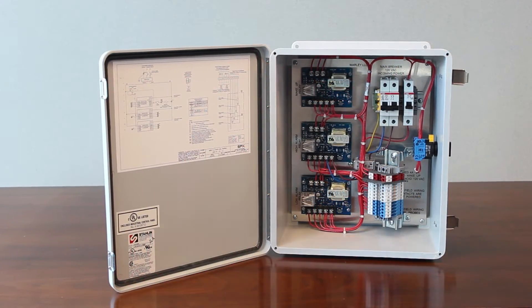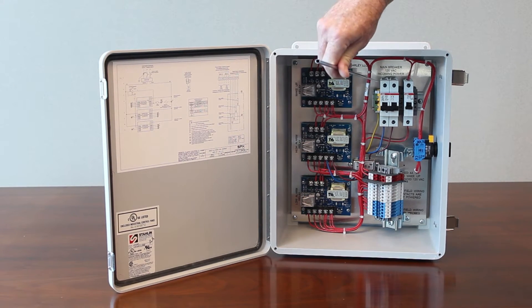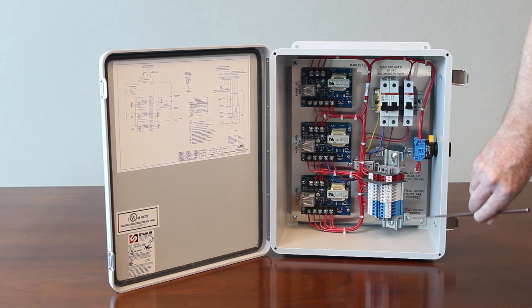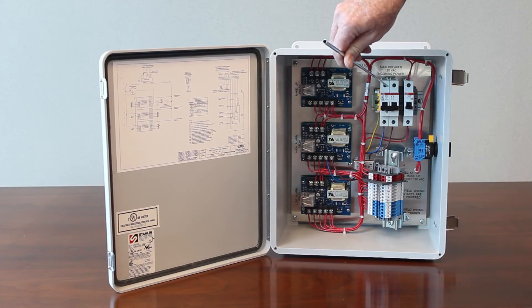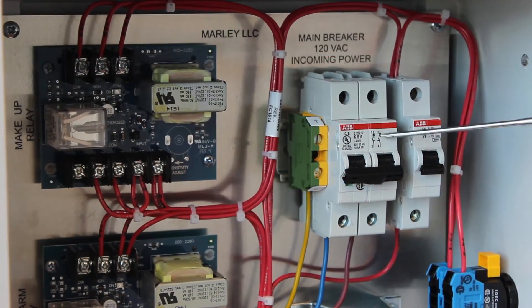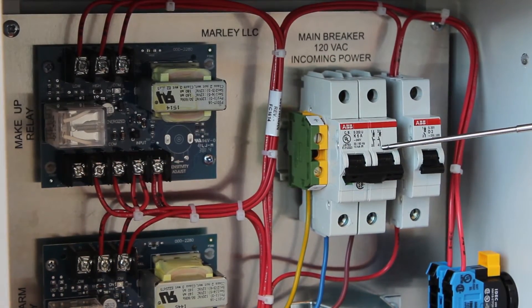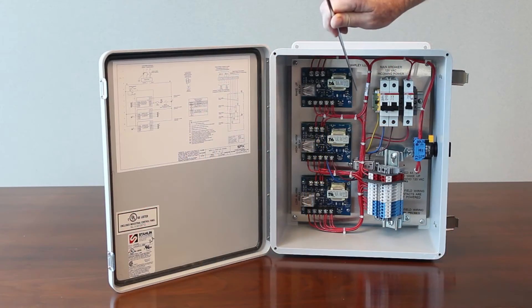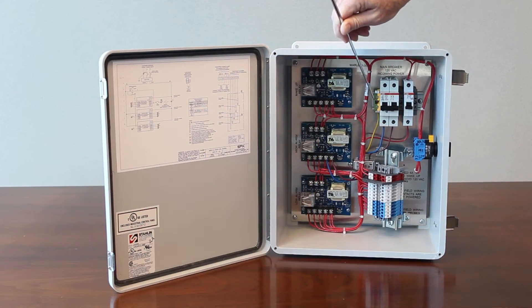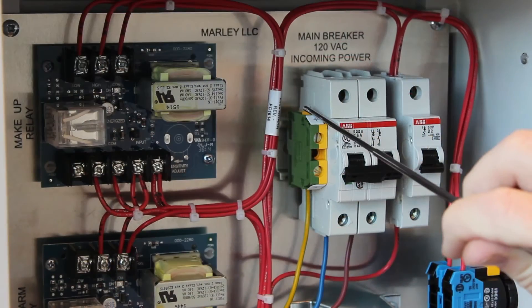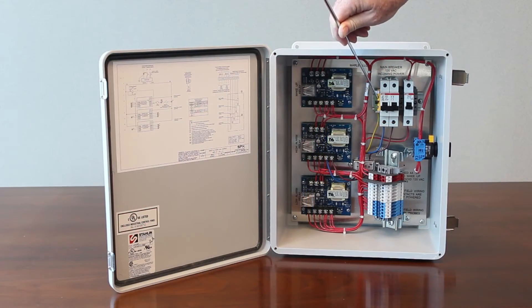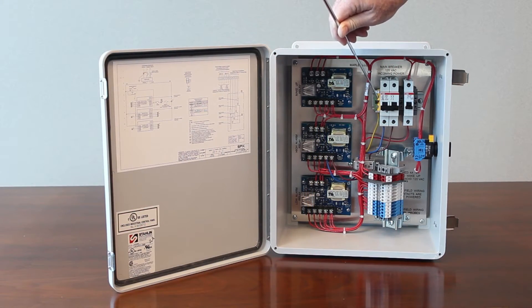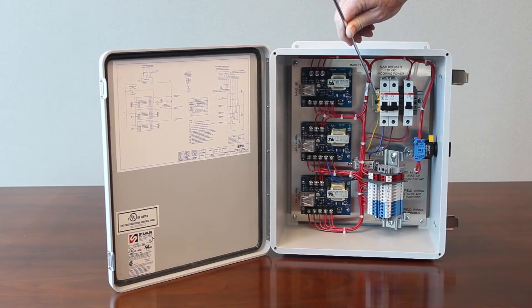Additional field wiring is your main power which comes from the bottom up and over and into the top of your two pole main circuit breaker, hot and neutral. Inside here there's a place to land the ground which is right here. We need six amps of service to power this breaker and the controls inside.